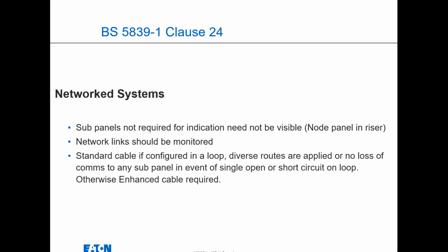If you're looking at bigger systems, network systems, the sub panels, so say in a riser cupboard, they don't have to have any indication and they don't need to be visible. But obviously all their network links should be monitored. And again, you can use standard cable if it's in the loops, but the standards will tell you when to use the enhanced fire cable.